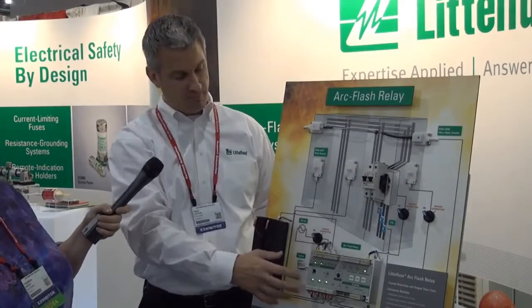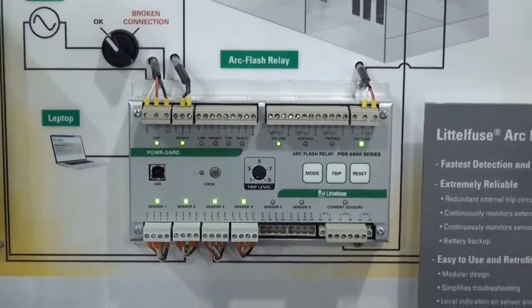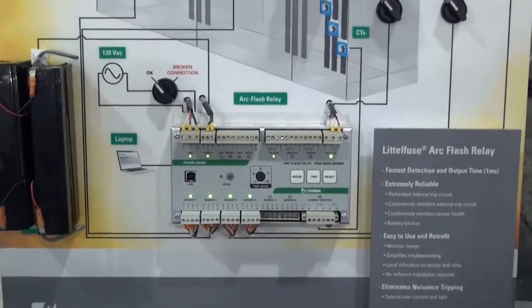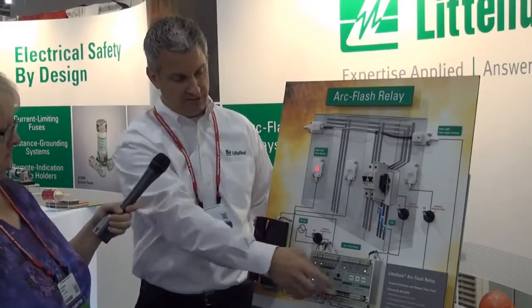And other possibilities here, so with the relay here, it sees the light, it sees the overcurrent, sends out a signal, and if for some reason the circuit breaker wiring isn't correct, the trip coil wiring, for example, say it's broken or becomes loose, the relay will see that condition and send an alarm out to the user saying, look, we see the light sensors are working properly. However, if I see an arc flash, I cannot trip because I'm not wired correctly to this circuit breaker here. Now, I'll go ahead and put that back in the same condition here. And every input and output going into the relay is monitored the same way that the sensor and the trip coil is monitored. So if any input or output wire comes loose out to the CTs, it will create an alarm condition. So the user can come out and repair the problem there. And I'll go ahead and demonstrate here.